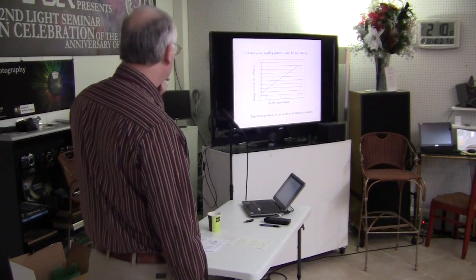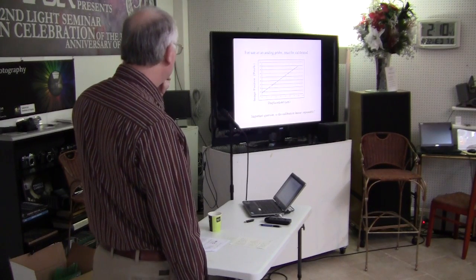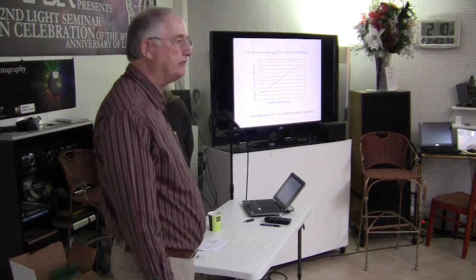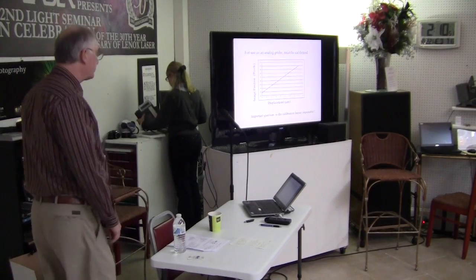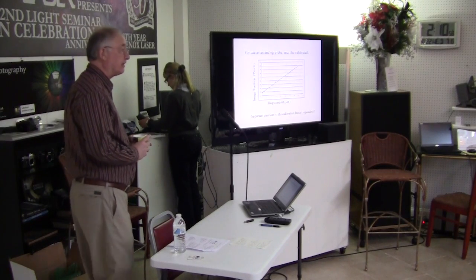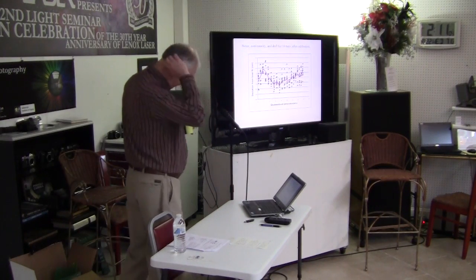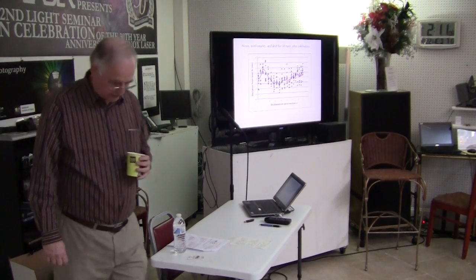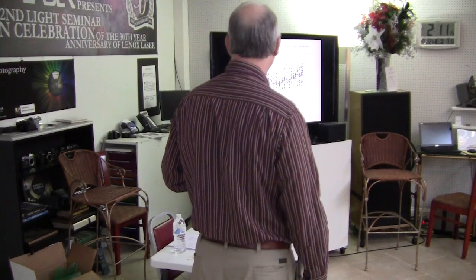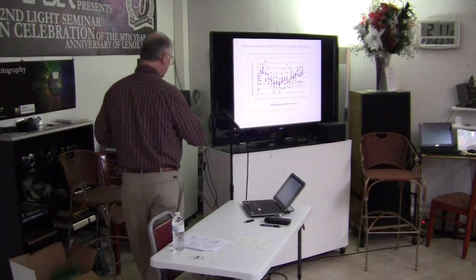Now, the calibration is very good. This is running it up against a laser, and that's about 110 pixels. And in the bottom is micrometers. You can't possibly see that the end of the scale is 18 micrometers. So we're talking about a very, very linear calibration curve. We're measuring things that are very, very small. This is pretty much with 10 runs, because if it works once, the only thing you can do is run it 10 more times to try to figure out what's really going on. This to that is 40 nanometers.